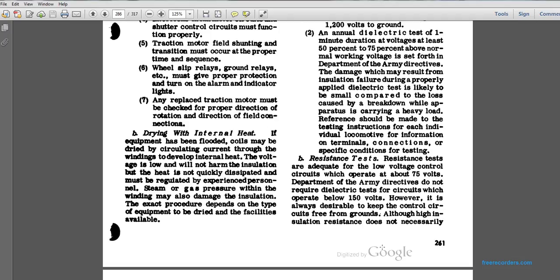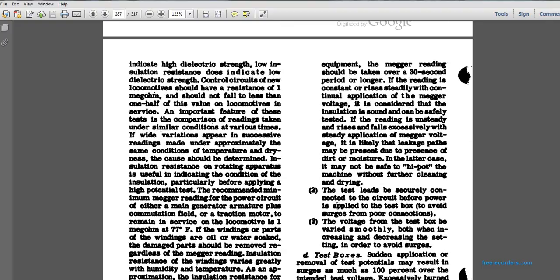B. Resistance tests. Resistance tests are adequate for the low voltage control circuits that operate at 75 volts. Department of the Army directives do not require the dielectric test for circuits which operate below 150 volts. However, it is always desirable to keep the control circuit free from grounds. Although high insulation resistance does not necessarily indicate high dielectric strength, low insulation resistance does indicate low dielectric strength. The control circuit of a new locomotive should have a resistance of at least 1 megohm and should not fall below one half of this value on a locomotive in service.